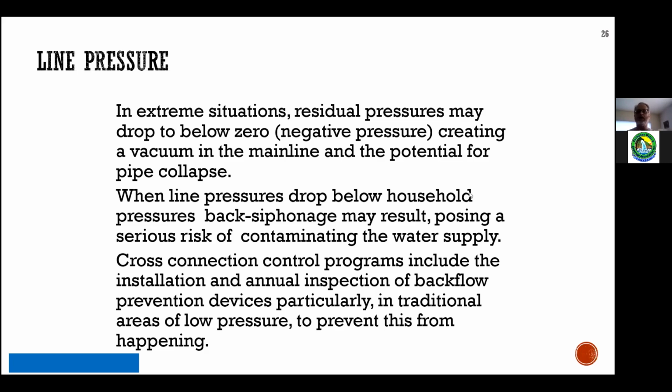So one thing that an emergency can do, you can isolate it and restore the grade line. But if it's demand, if it's hot weather, agriculture, or different population growth, we need our engineers and our system designers to have taken that into account so that the line pressure never drops below that minimal level of 140 kPa.